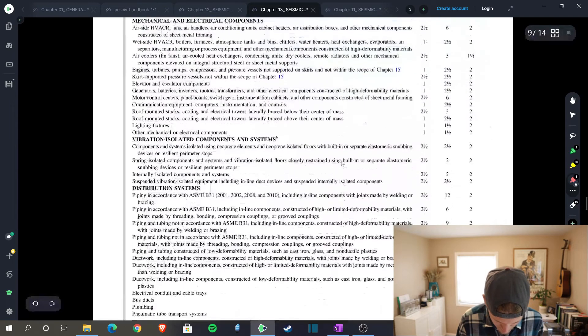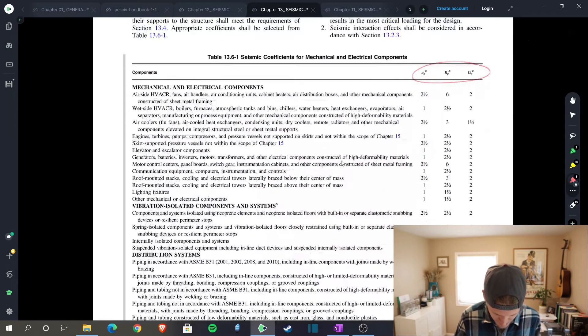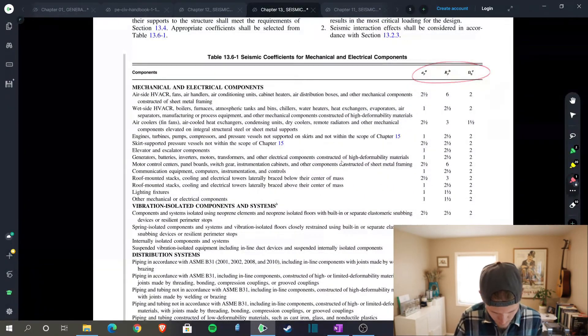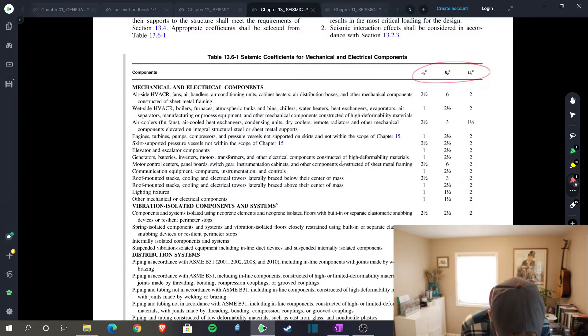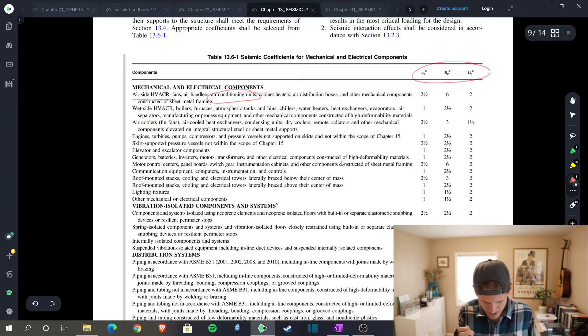Distribution systems, vibration isolated components and systems, mechanical and electrical components. And what we have today is an air side HVAC unit, because if you look further you'll see that is defined as an air conditioning unit, which is what we have. So we get to use an A of two and a half, an R of six, an Omega of two.